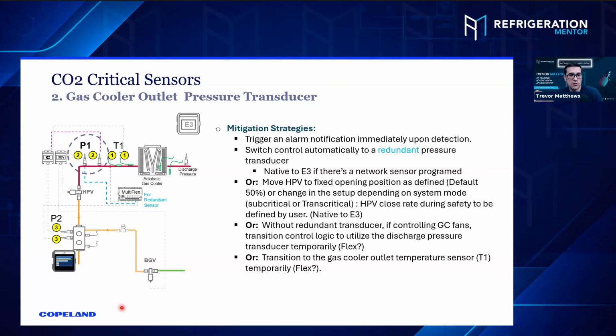And it makes sense, right? Because you should not have much of a pressure drop anyway. And with CO2, 15, 20 psi is not a big deal. Like, that's not a big deal. Right. No, exactly. It's a rounding error when you're talking 1,000 pounds, you know. Okay, I love that. And then the other mitigation is you can transition the gas cooler outlet temperature to T1, but you still don't have your pressure, though you can try to control off T1. So it becomes a little more complicated. The other two provide you some reasonable flexibility.